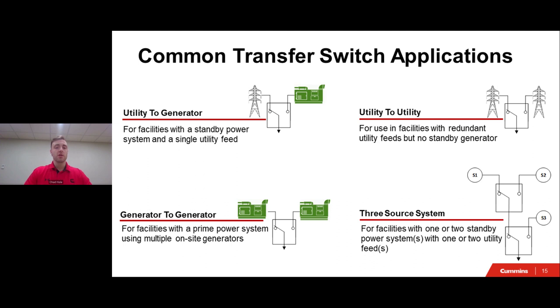And then lastly, we have a three-source system. In a three-source system, it requires two transfer switches, and these three sources can be a combination of many things. You could have two utilities with a generator, or you could have the opposite of two gens and a utility, and then you have two transfer switches monitoring all the sources. So you'll have one transfer switch monitoring source one, source two, and then another secondary transfer switch monitoring source three, and then they can switch appropriately as needed if something goes wrong.